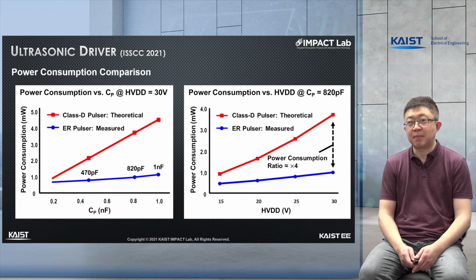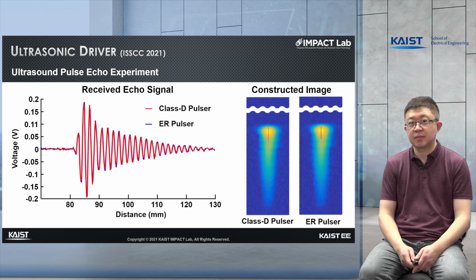This result shows the power consumption of the developed pulser IC in comparison with the power consumed by the conventional Class D pulsars. We can find that the power consumption can be reduced by a factor of 4, especially at high capacitance and high voltage conditions. Looking at the ultrasound pulse echo experiment result, the proposed pulser IC achieved the same performance as the conventional Class D pulser while consuming a lot lower power and energy.